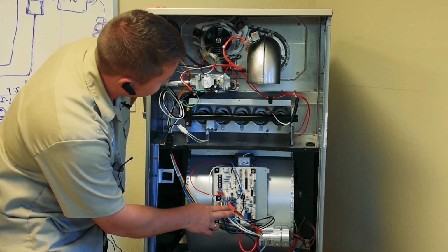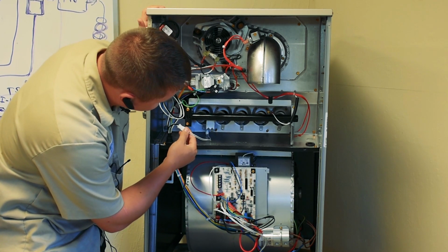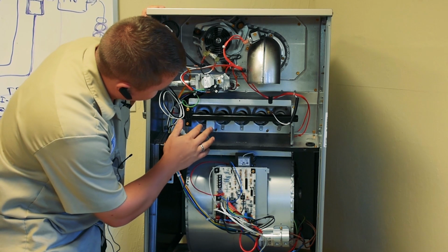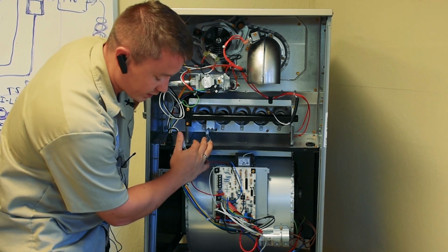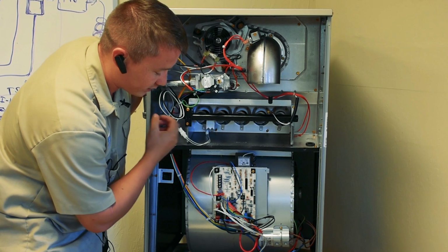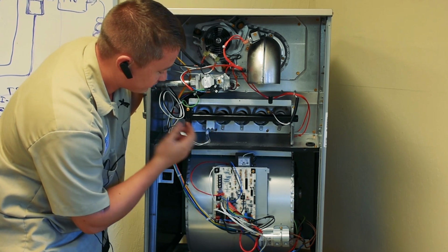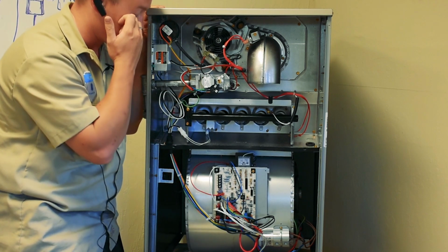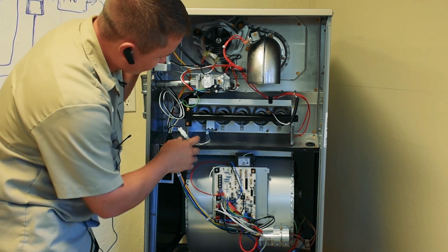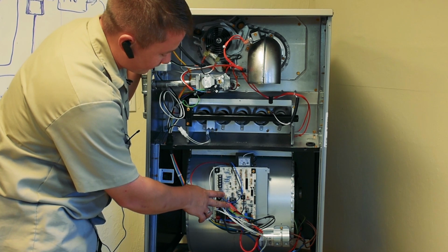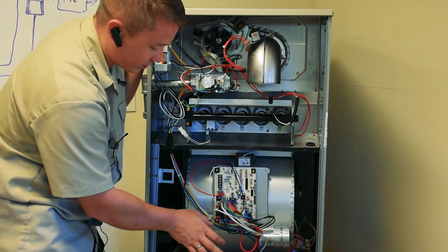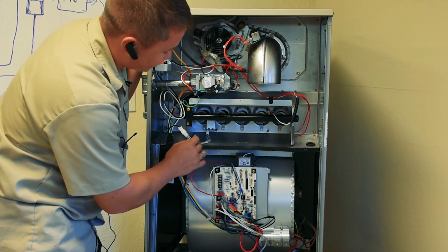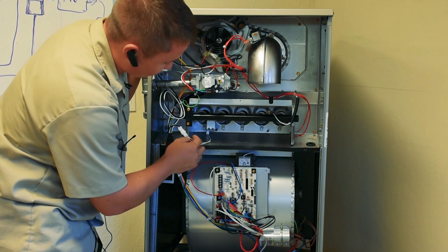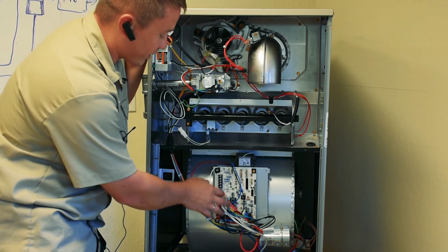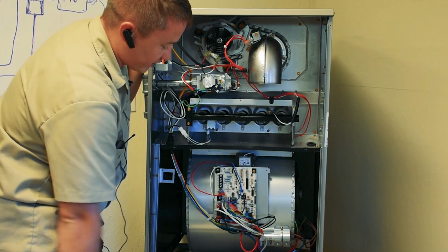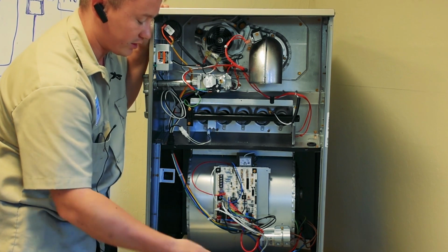The next relay will send the 120 volts power to the igniter. The igniter will ignite, getting a red or yellow color, you will see that. Then the control board, depending on the model, could sense the changing resistance of this igniter, or just will run this igniter by time, like 10 to 30 seconds. It's running for like 30 seconds.